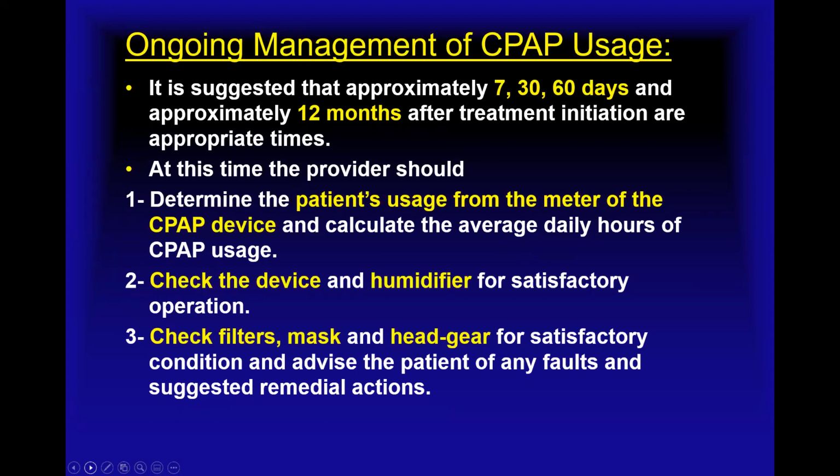Check the device and the humidifier for satisfactory operation. Check the filters, the mask, the headgear. How are you cleaning it? How often are you cleaning it? What are you using to clean it? And at some point, it's been cleaned so many times and used so many times that it needs to be replaced.